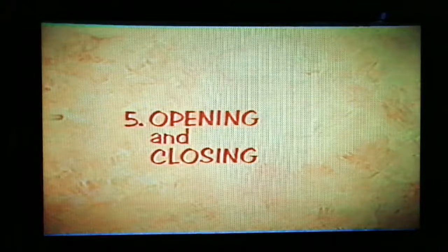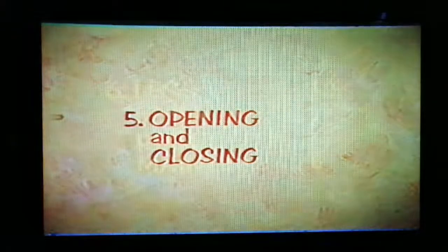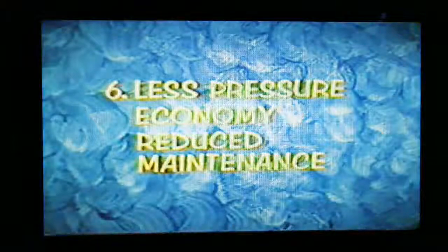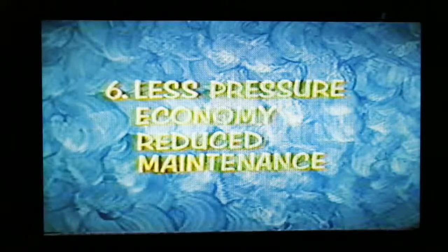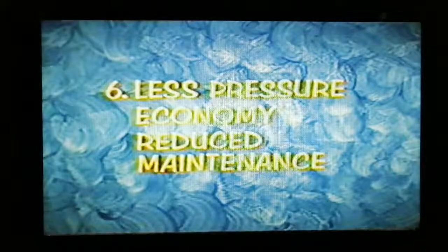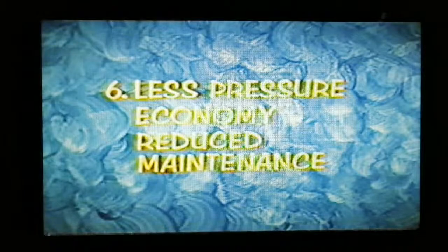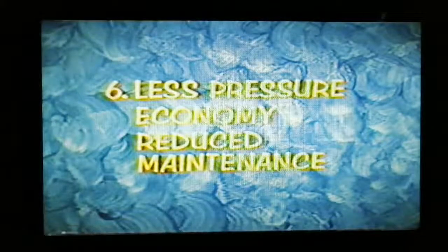Blowdown is the pressure drop between the opening and closing of a safety valve. An electromatic relief valve requires only about 1% pressure drop in comparison to the minimum of 3% in regular safety valves. This results in less steam loss and reduced safety valve maintenance, since constant popping of the safety valve makes it unreliable.